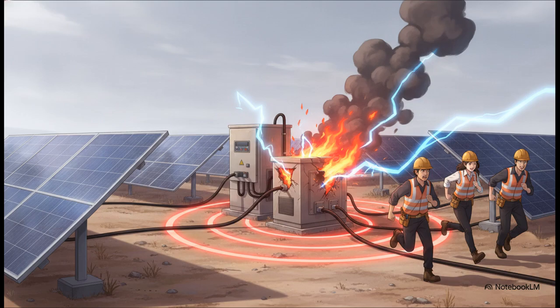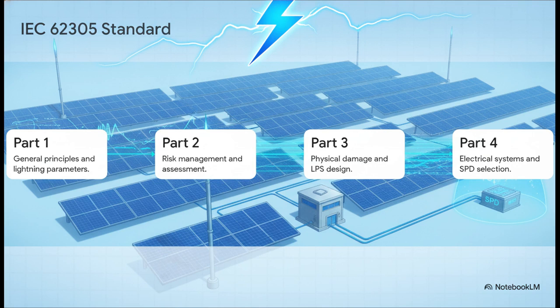The danger isn't just at the exact point of impact. Lightning induces massive voltage surges that travel through your cables, destroying equipment way far away from the actual strike. And most crucially, an unprotected plant risks human lives by creating fatal step and touch voltages right on the ground around the strike area. To stop this, we rely on the formidable IEC 62305 standard.